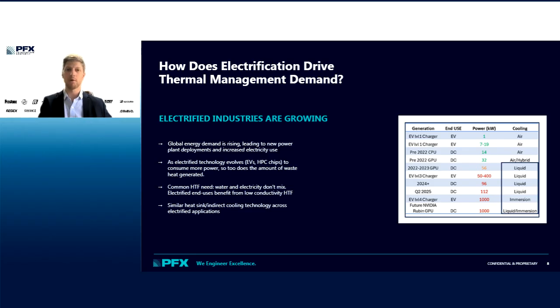So we've gone from air cooling being able to handle the thermal loads for everything in the industry, to now having to use liquid cooling. Within the next 2 to 3 years, the goal is to move from 112 kilowatts all the way up to a megawatt of power per rack.